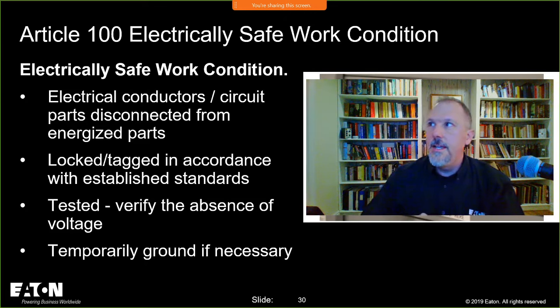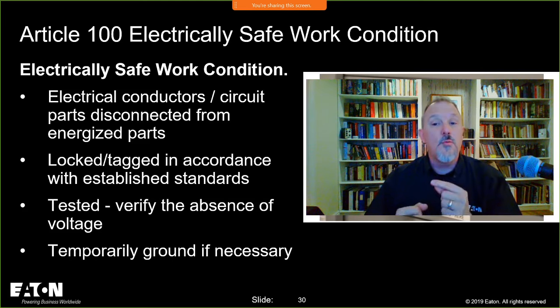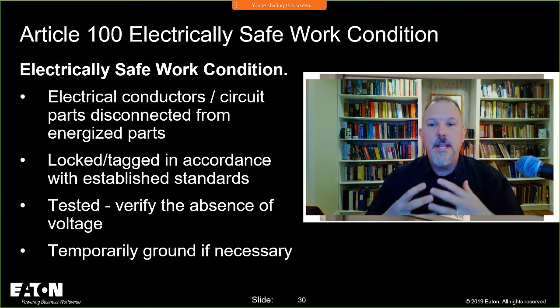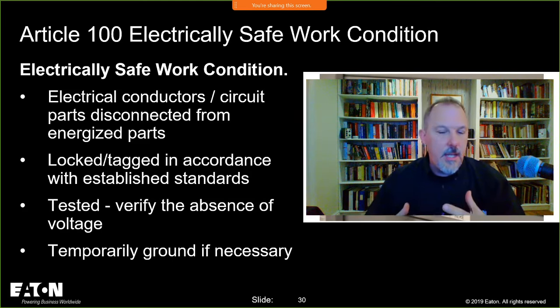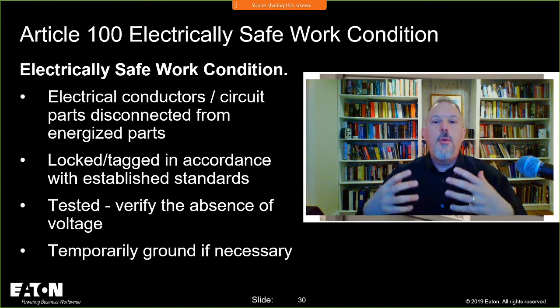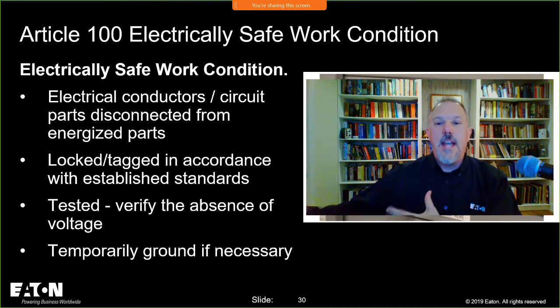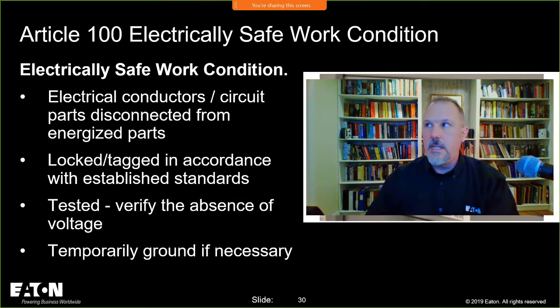The National Electrical Code and the Electrical Safe Work Practices both use Article 100 to put all of their definitions. There is a definition for electrically safe work condition, and there's an important reason, because 70E tells us that you just can't turn it off. You have to go through the process to establish an electrically safe working condition.